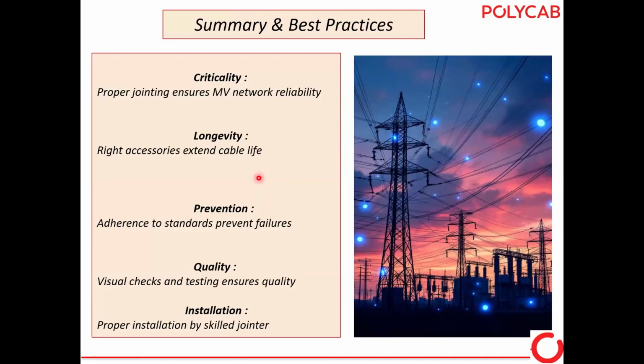So let's conclude this summary. My last slide is there. Cable accessory cost-wise is not high, but if something happens to them, the cost is very high. So it's very critical. That's why we should see this product from a criticality point of view. If the right cable accessories are used, cable accessory life will definitely increase. We have to adhere to all the standards so that failures will not happen. Quality and visual checks have to be done. But jointing has to be done by skilled jointers only.